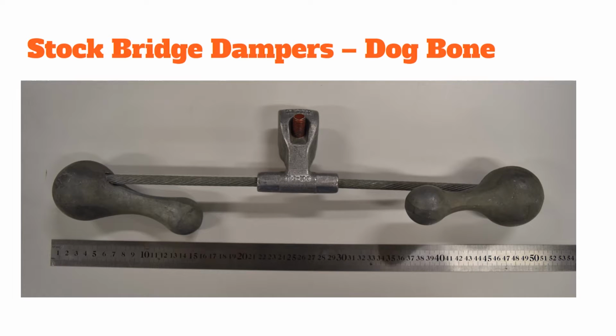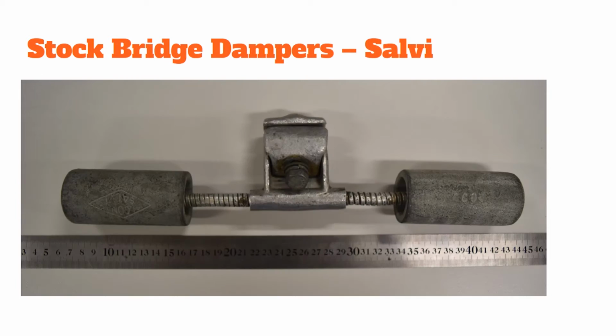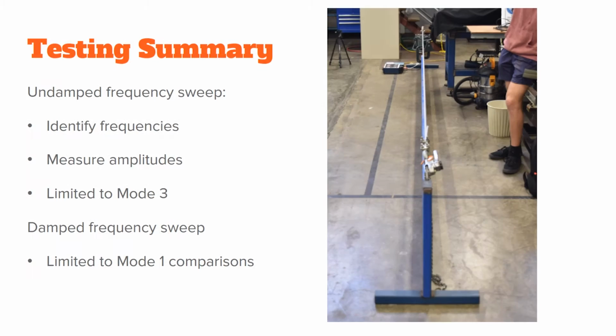The offset introduces torsional damping that dissipates more energy and is particularly useful in 3-dimensional applications such as Aeolian vibration. The Salvi damper has the 2 masses centered in the vertical plane, and although it lacks the torsional vibration mode, it was still effective over a considerable range of frequencies. The undamped testing wasn't able to distinguish anything past mode 3, and we were only able to get decent damping comparisons in mode 1 because the amplitudes at higher modes just became too small.